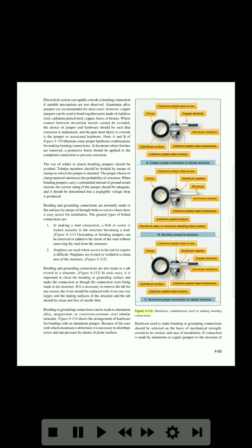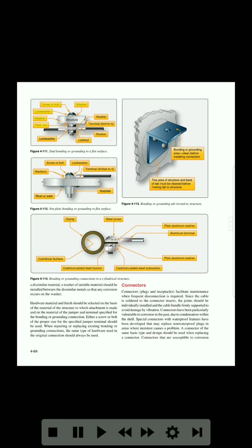Figure 4-110. Hardware combinations used in making bonding connections. Hardware used to make bonding or grounding connections should be selected on the basis of mechanical strength, current to be carried, and ease of installation. If connection is made by aluminum or copper jumpers to the structure: screw or bolt, washer, lock washer, plain washer, nut. Structure. Washer. Terminal, limited to 4. Washer. Lock washer. Lock nut.